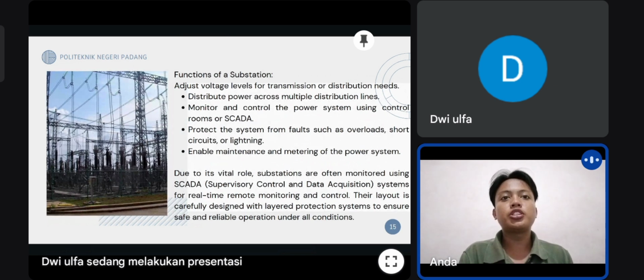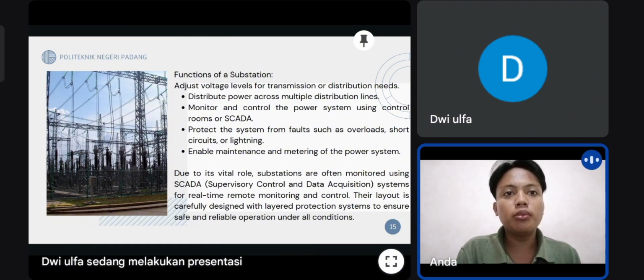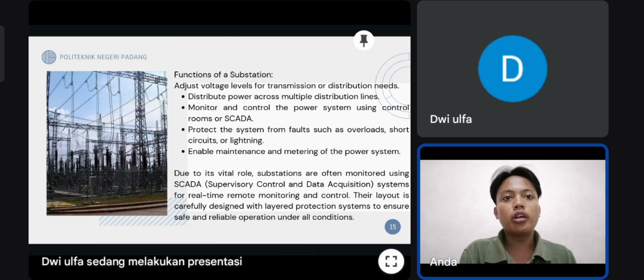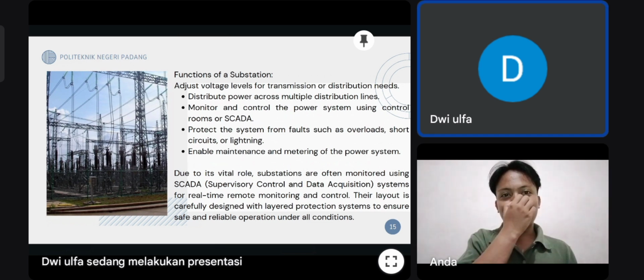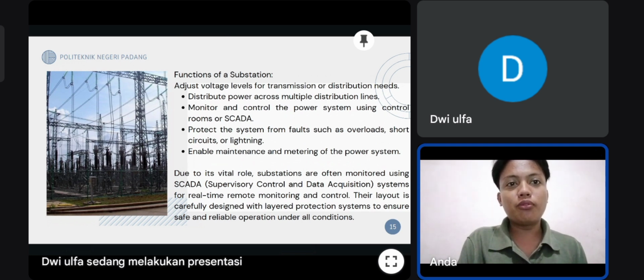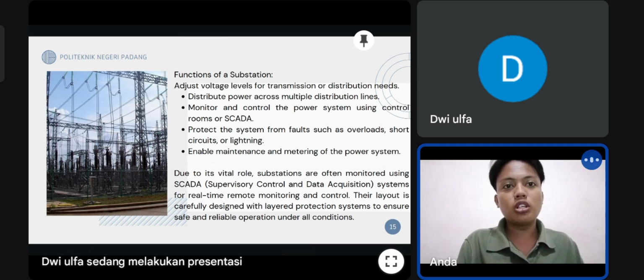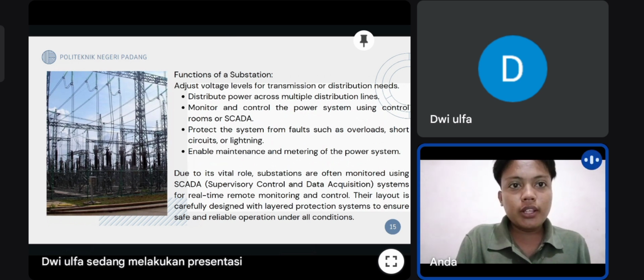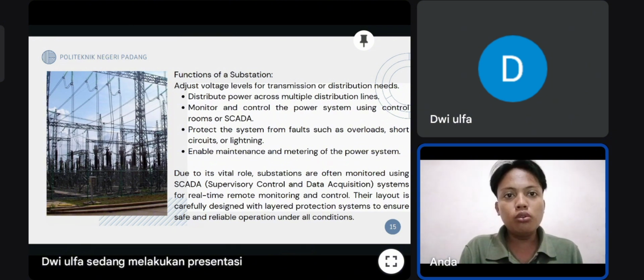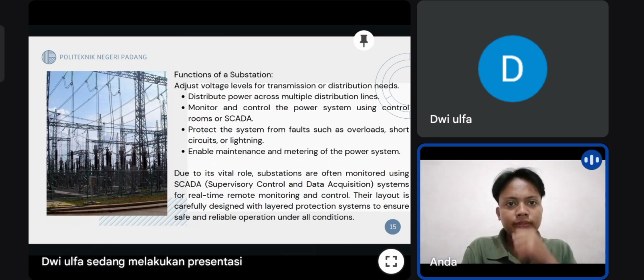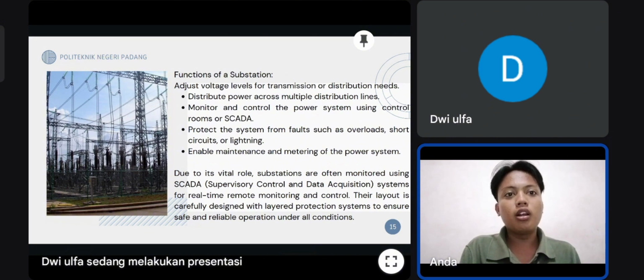Functions of a substation. Adjust voltage level for transmission or distribution needs. Distribute power across multiple distribution lines. Monitor and control the power system using a control room or SCADA. Protect the system from faults such as overload, short circuit, or lightning. Enable maintenance and metering of the power system. Due to its vital role, a substation is often monitored using a SCADA system for real-time remote monitoring and control. The layout is carefully designed with layered protection systems to ensure safe and reliable operation under all conditions.